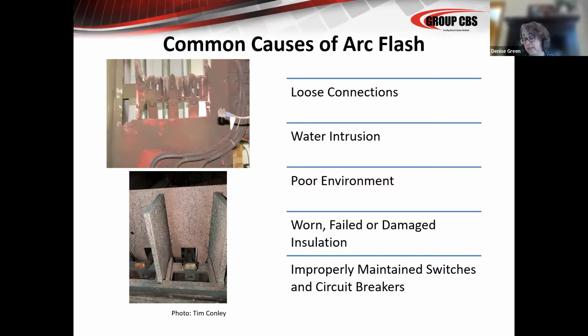Poor environment is a very large portion that affects maintenance and breaker maintenance cycles. If you're in an environment where there's a lot of particulate matter, that environment is going to affect your maintenance schedule and also affect the condition of the breaker over time. Worn, failed, or damaged insulation is a situation, and then obviously improperly maintained breakers, or breakers where the maintenance isn't happening frequently enough, can cause arc flash situations to happen.